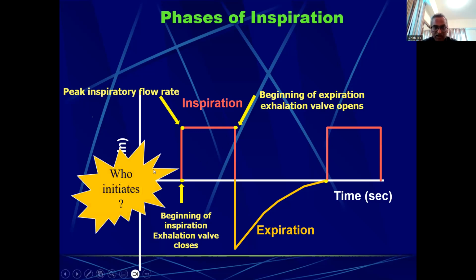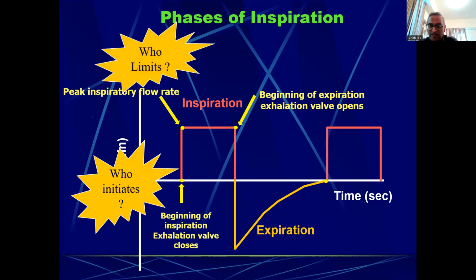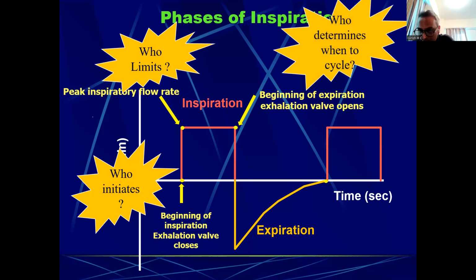So the first question is here, at the beginning of inspiration: who initiates the breath? Suppose you are on a ventilator. Does the patient initiate the breath or does the machine initiate the breath? That is the first question you have to ask. Second, what is the limit? As we talked about, whether it is a pressure limit or a volume limit. And third, who determines when to cycle? Like, I've had enough, I want exhalation. Does the machine determine that or the patient? If you understand these 3 questions and 3 concepts, every mode will be easy. All modes are based on these 3 important concepts.